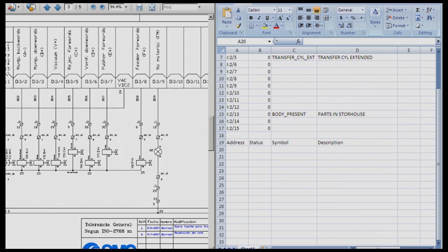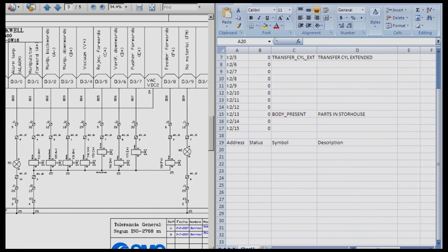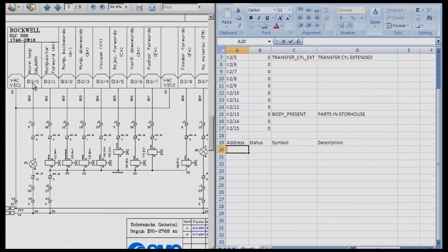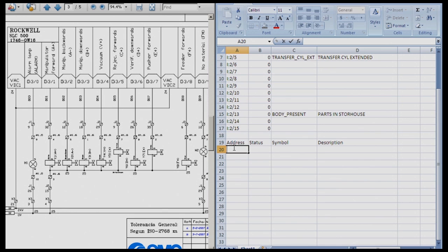This is much easier when you have both windows tiled so that you do not make any mistakes. If we look at the screenshot here, O colon 3 slash 0 is our alarm lamp. So we know that that is the first address on our card. So we type O for output colon 3 slash 0 and we hit enter.